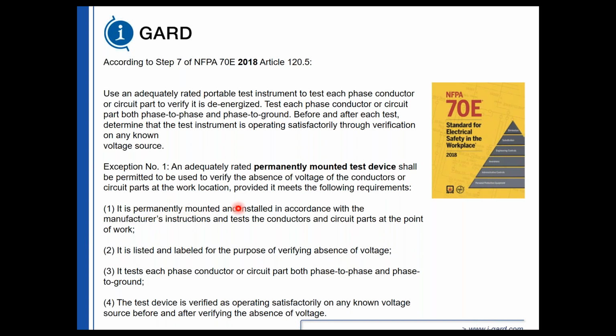It is permanently mounted and installed in accordance with the manufacturer's instructions and test conditions, conductors. It is listed and labeled for the purpose of testing for the absence of voltage. It tests each phase to ground and phase to phase, and the test is verified with a known voltage source.